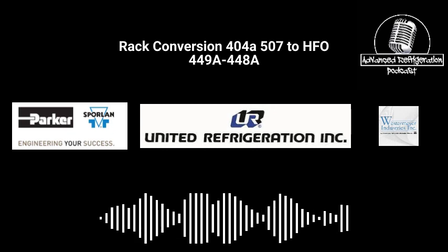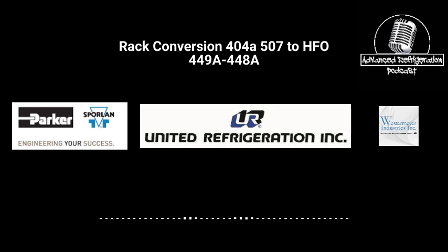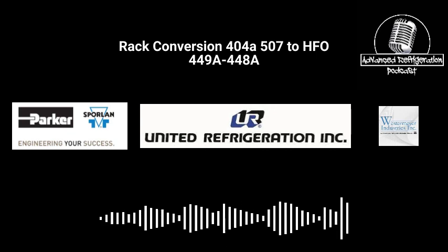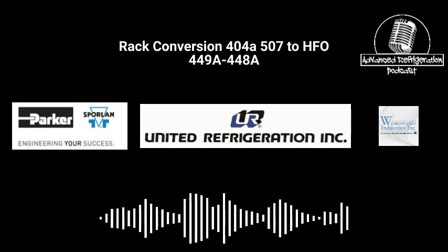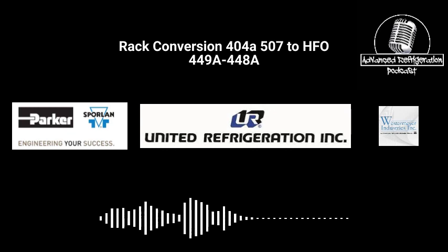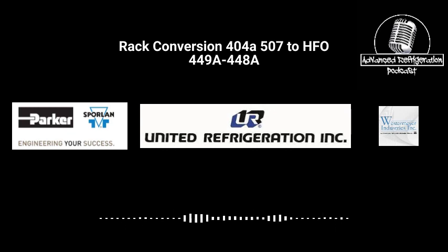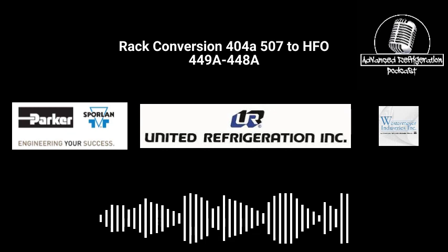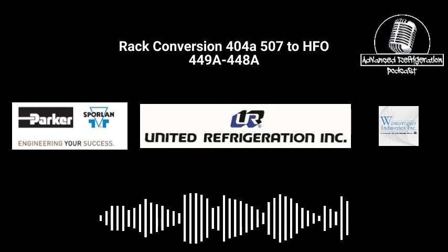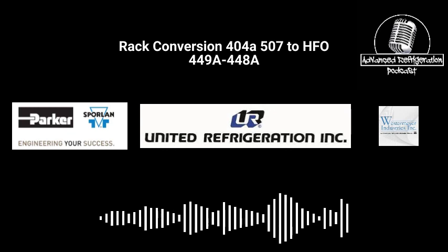If you're doing one of these jobs and you're taking the gas out and doing a gas changeover, everything's already there, the fitters are already on site — just change the high side ball valves. For what it's going to cost to change the high side ball valves, you're eliminating leak potentials and eliminating ball valves that probably don't hold. If the rack is older than 10 years old, let's be honest, those ball valves probably don't hold all the way, so why not just eliminate that right away?